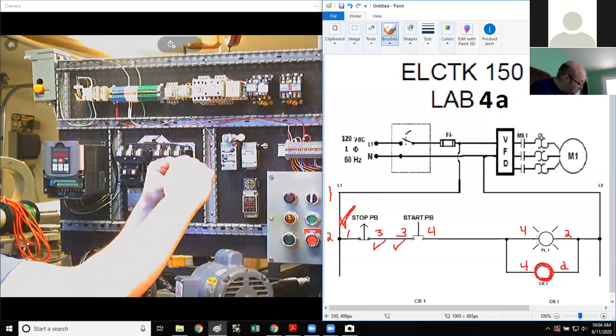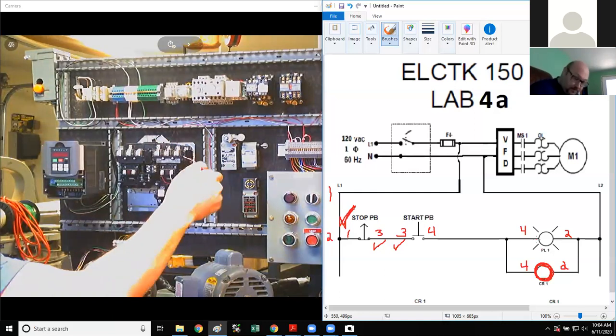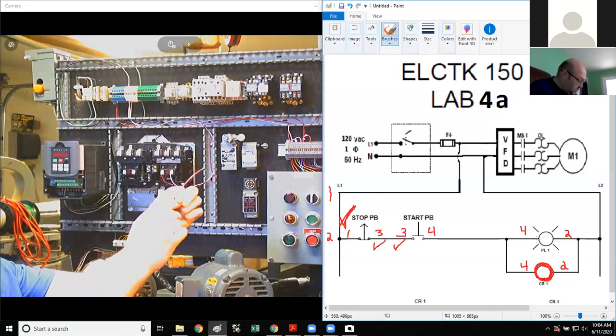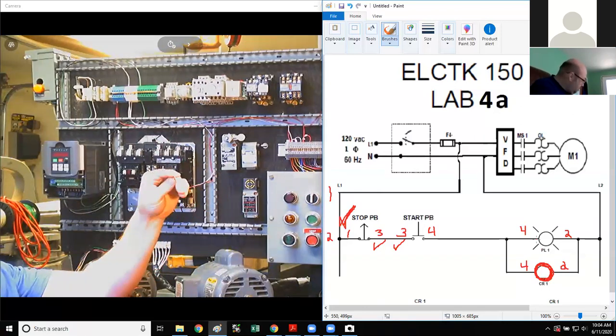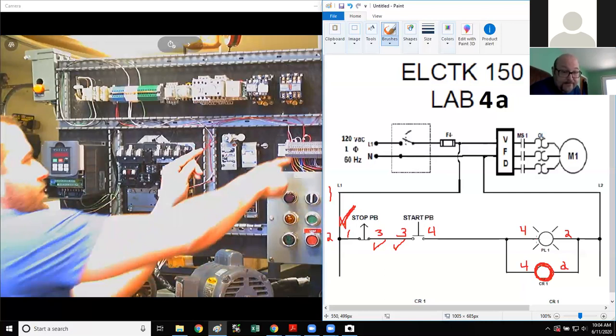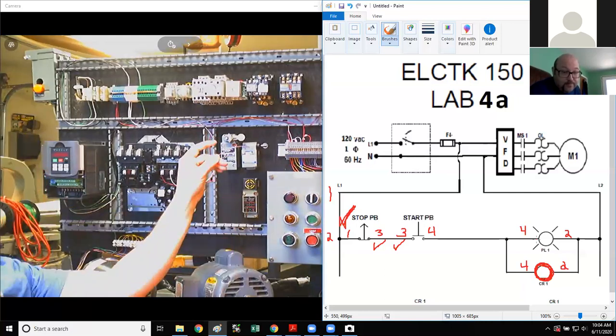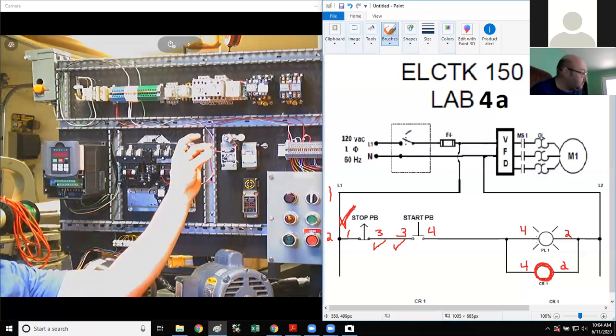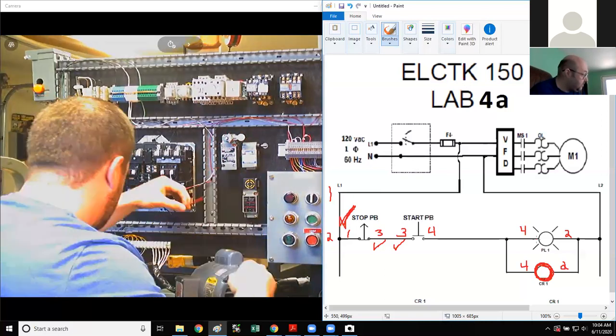One thing I've seen some of you guys doing is taking one wire number and putting it right in the middle of the wire, which is fine for little jumpers since they just go across here. But if I take a wire, which I'll have to do to go to the coil, that's really long, it's a good idea to label both ends for obvious reasons. I'll show you that here in a minute. So this is going to be wire number 4.